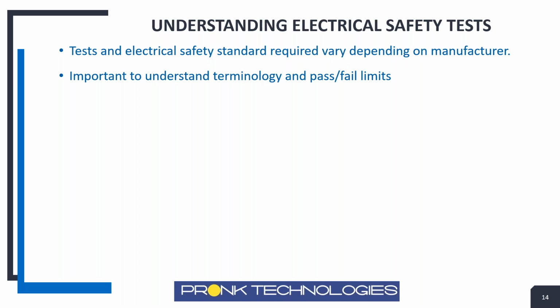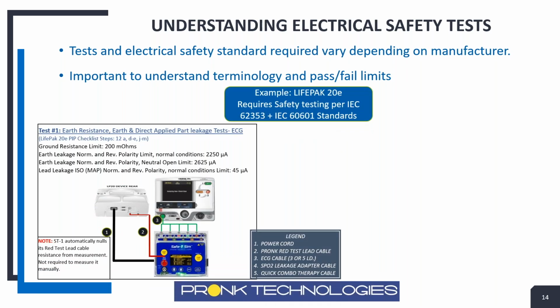But if you're going to follow the manufacturer standards, it's important to understand some of these differences, especially the pass-fail standard. This is an example, and there's nothing wrong with this device. It's just the way they designed it, and they require their testing to be done a certain way. This is an example of a LIFEPAK. The LIFEPAK 20E, I think they recently took it off the market, but there are still a lot out there. What's interesting is they require the safety tests to be done according to two different standards.